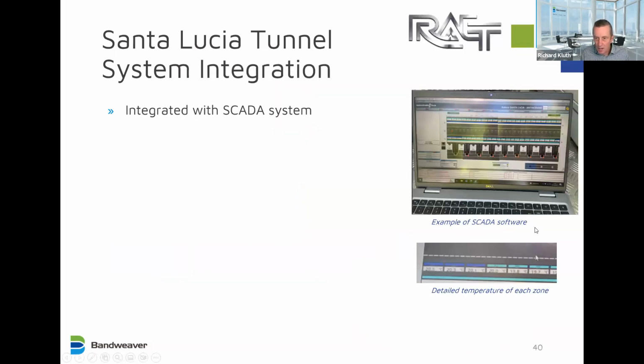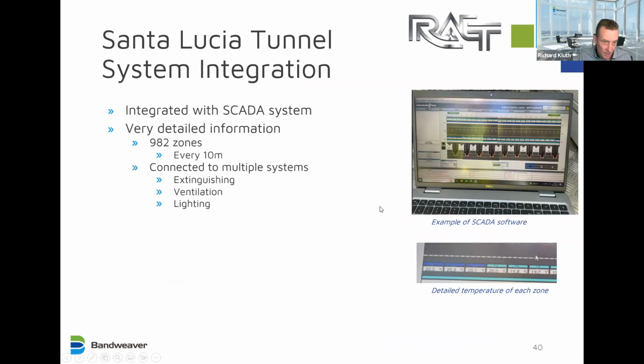Integration with the SCADA system. We have a screenshot of the SCADA software here. We have a close-up where you can see the actual temperature is being built in on a zonal basis. So you see the maximum temperature of each zone in there. And there are a lot of zones for this project, 982. They have it every 10 meters. That was dictated by the extinguishing system.